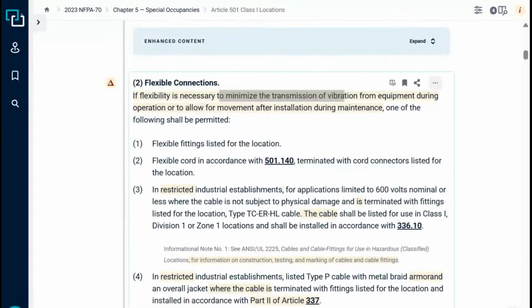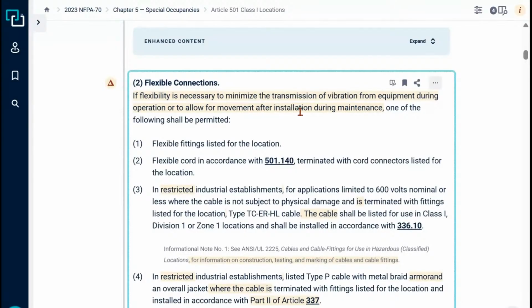Here's what it says: one of the following shall be permitted. Number 1 says flexible fittings listed for the location. Manufacturers make flexible fittings that can work with the type of wiring method you're using, provided that they're listed for the location. So obviously the location is a Class 1 Division 1 location. So buy the fittings if it provides flexibility that is listed for that location. That's fine.